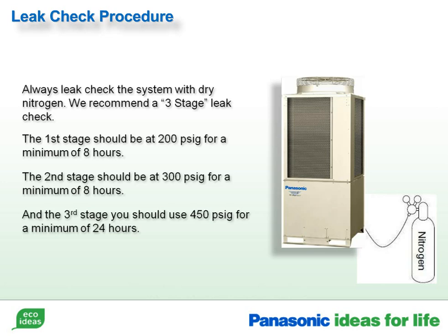Always leak check the system with dry nitrogen. We recommend using the 3-stage leak check method. The first stage should be at 200 psi, for a minimum of 8 hours. The second stage should be at 300 psi, for a minimum of 8 hours.